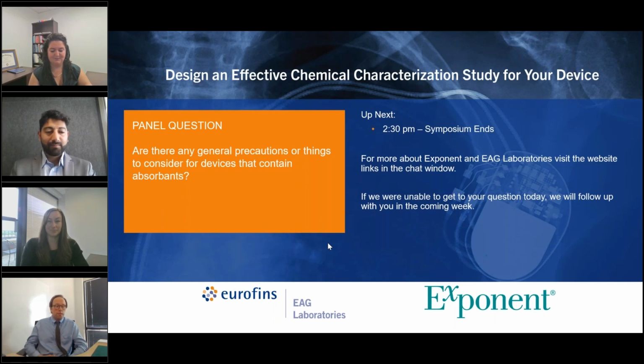Sure. So it's really important here that before you start the full study, you have to know how that is going to play out when you go to remove your solvent, right? A lot of times when you have something that's adsorbent, like a filter or something that'll retain solvent, typically you're doing a fill on the device, right? And depending on the size of it, you say, okay, I'm putting in 10 mils, right? And if 10 mils is just enough to complete your study, but you decant it and you only get 5 out, that's a problem, right? You don't have enough solvent to even analyze, right?